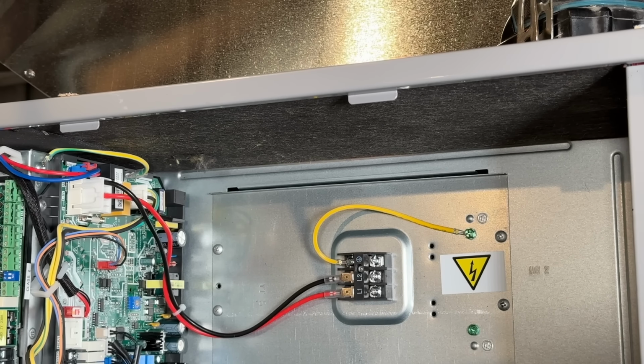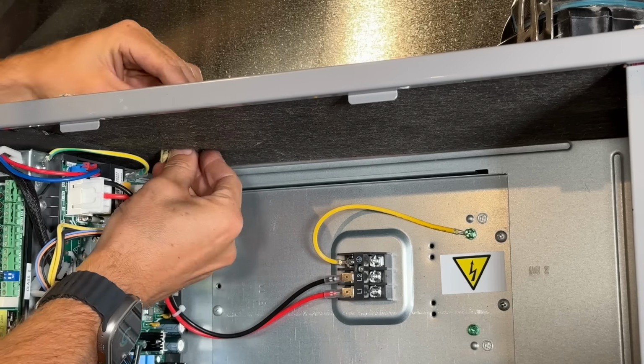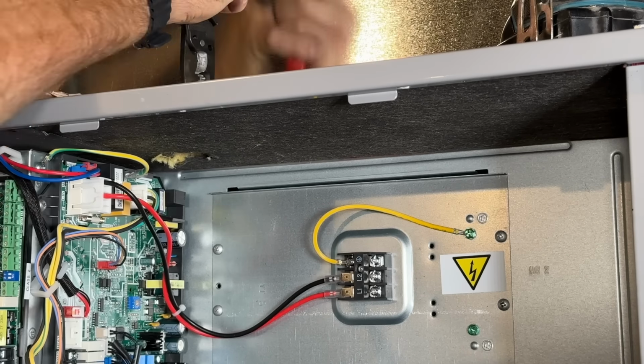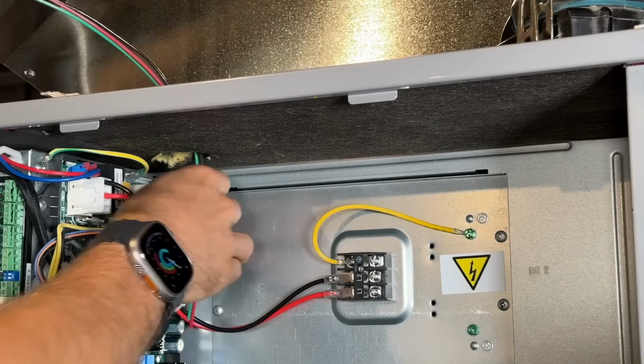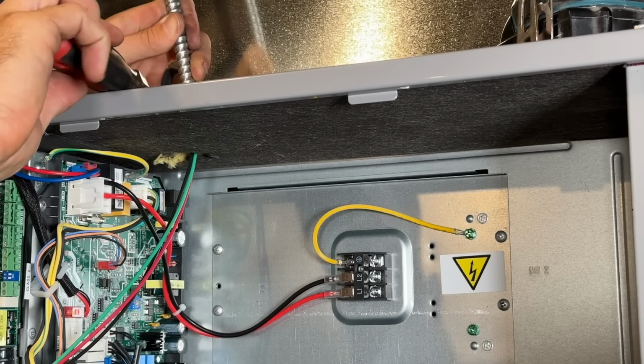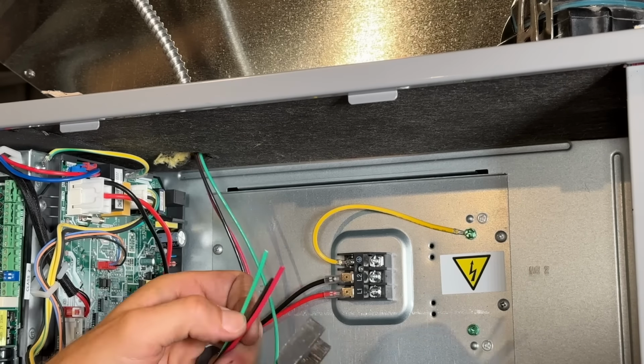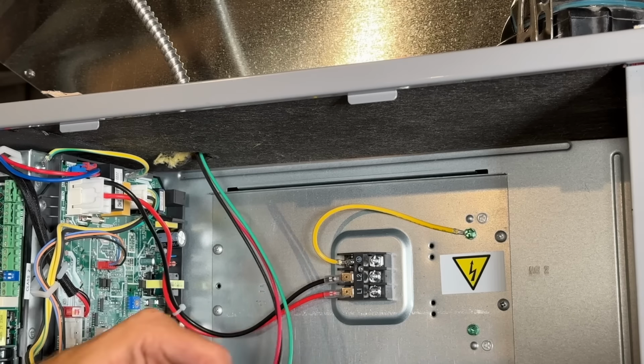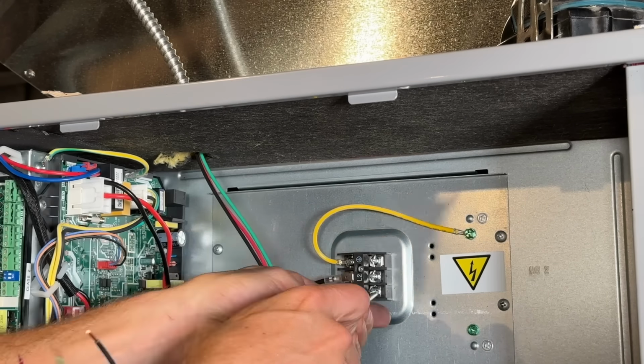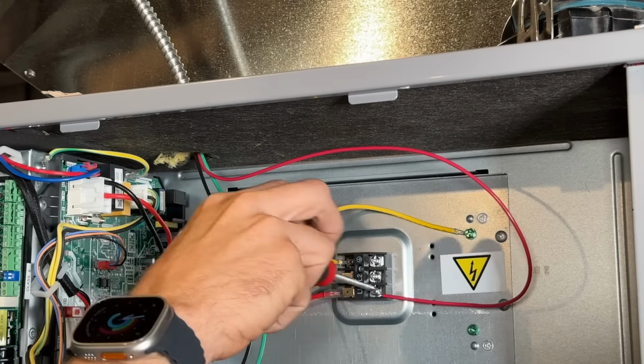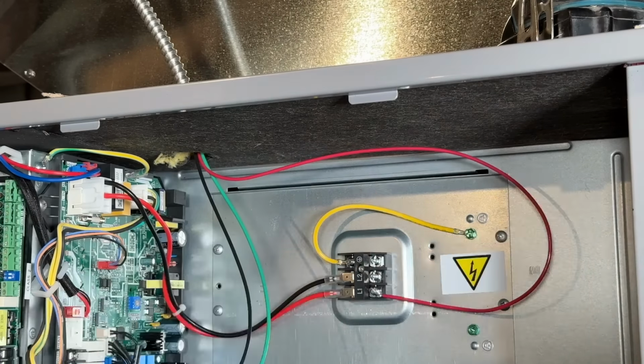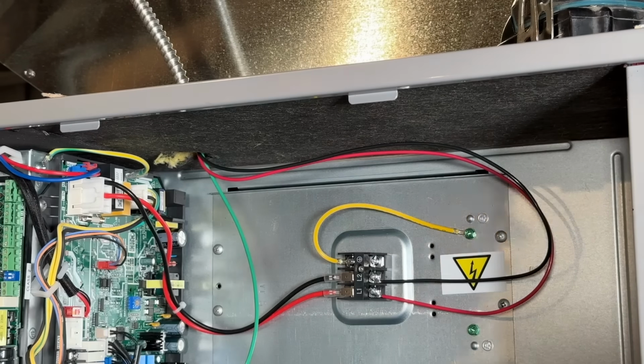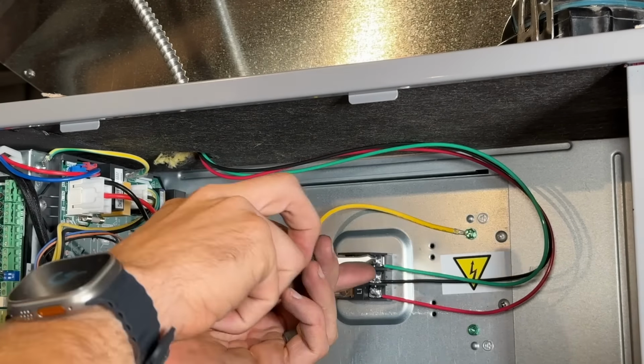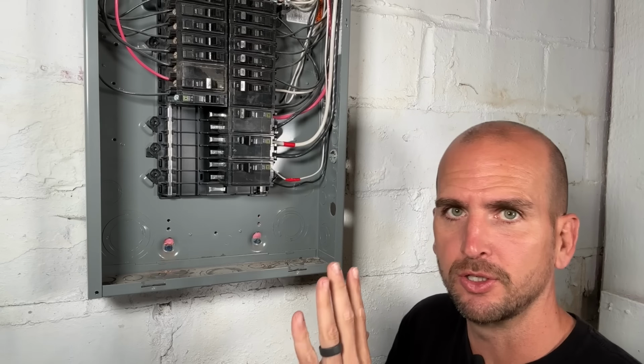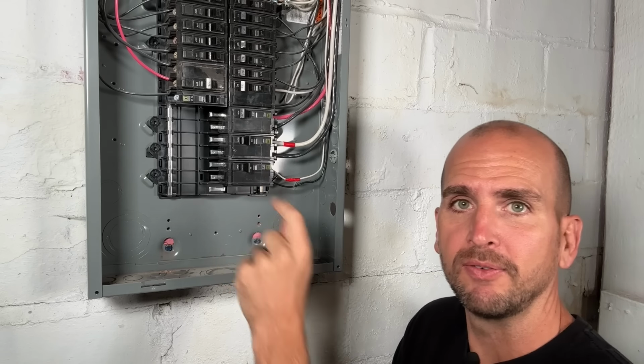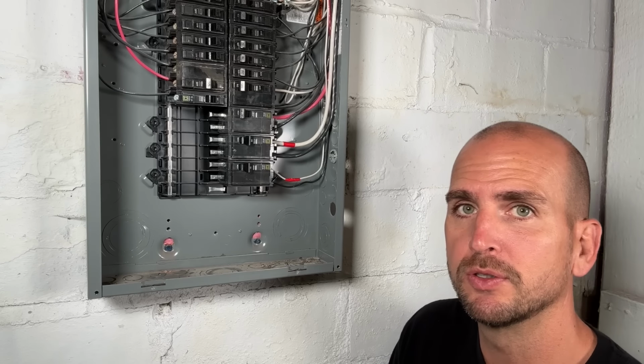And then we'll complete this side. This is the 15 amp coming into the actual unit, and it has a little bus bar here where we can connect our 2 conductors and our ground. So we'll have the 3 wires there. I'll strip those solid. And I'm not going to put anything on the end of these because the solid conductors can go under those plates and we can secure them down without any issue. And then the connections are completed back here at the panel for my 15 amp 240 volt circuit breaker.